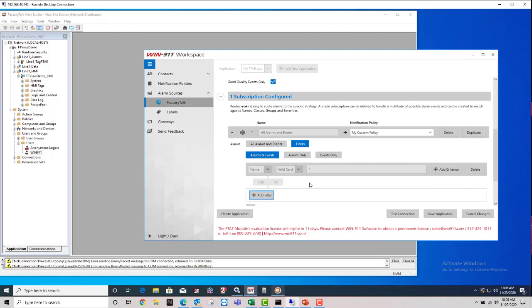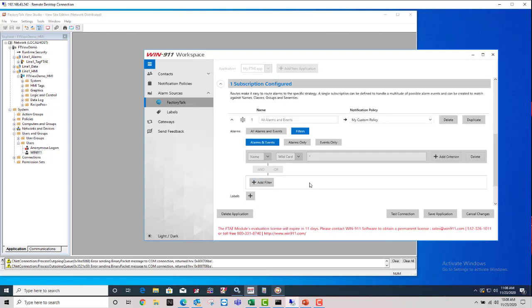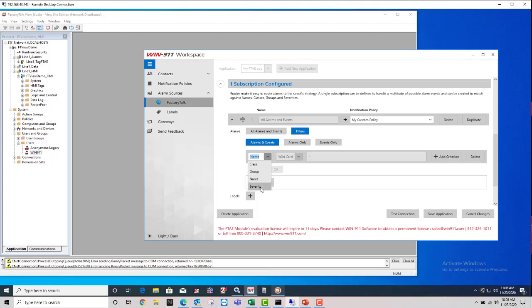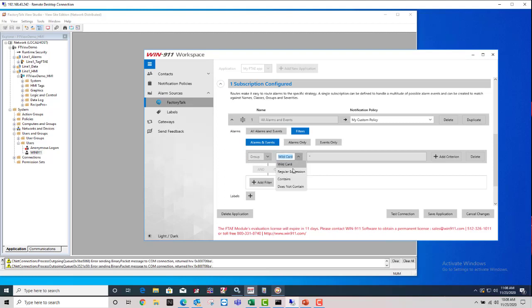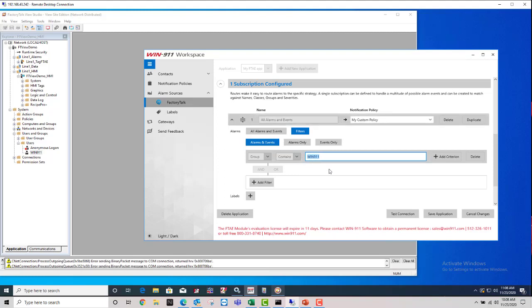So this is how you start building out your custom filters that are going to be pulling in those specific alarms that you want brought into Win911. So the first drop down, you can filter on class, group, name, severity. Those are the fields you can filter on. And then how to filter is by wildcard. You can do a regular expression. So for example, we will do a group and a group that contains the word Win911. So this is saying as long as it contains this text, it will grab and match those.